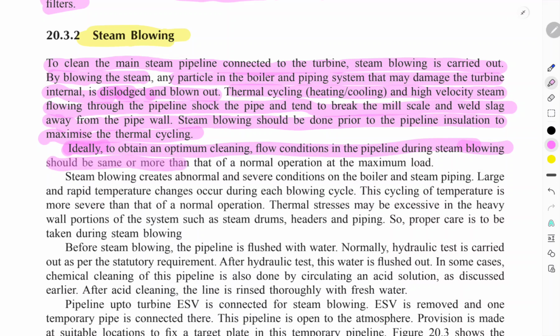the flow should be the same as or more than the normal operation at maximum load. The steam blowing creates an abnormal, severe condition. In the boiler steam pipe, large and rapid temperature changes occur during the blowing cycle. These cycles of temperature are more severe than the normal operation. Thermal stress may be excessively heavy in portions of the system such as the steam drum, header, and piping. Proper care is to be taken during the steam blowing.